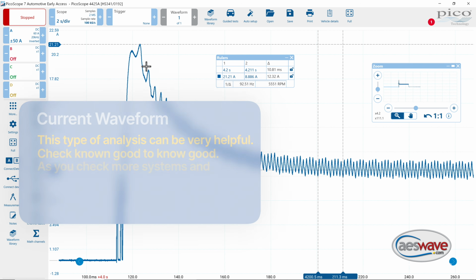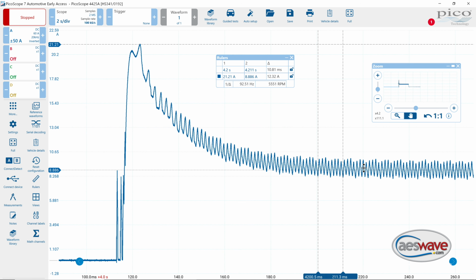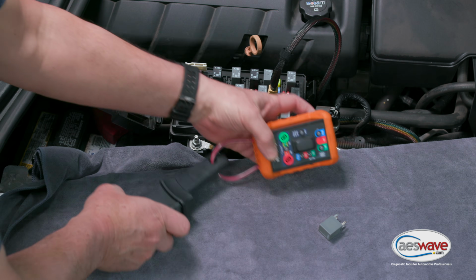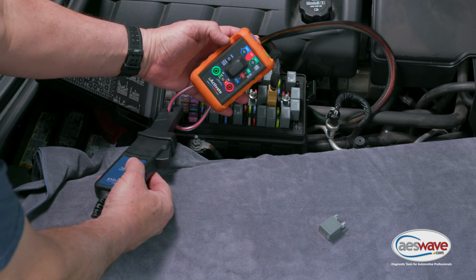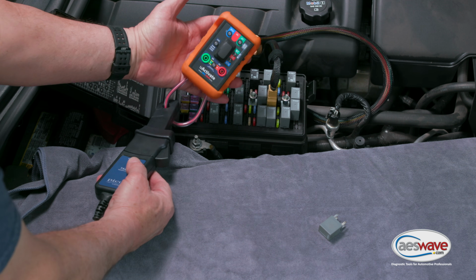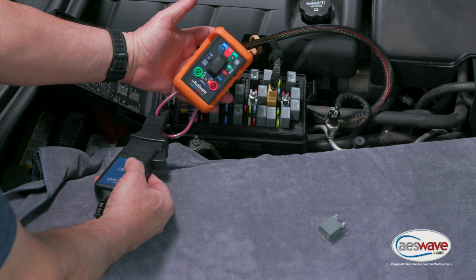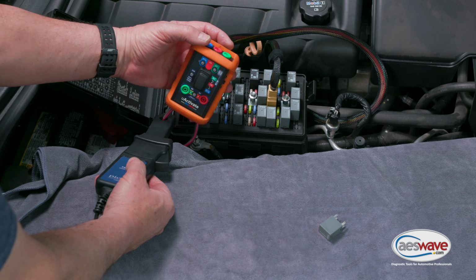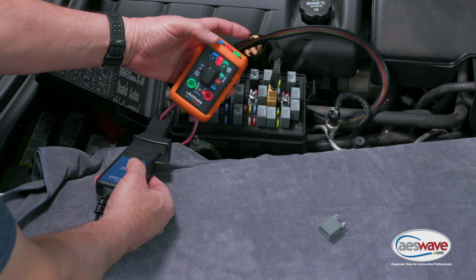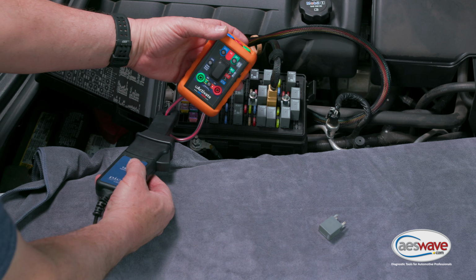We're hitting our peak amperage, 21 amps, that indicates a healthy circuit. And we've got nominal speed, and our operating amperage is about 8 amps. So as you can see, using the uActivate to get into the circuit and interrogate it makes it very, very convenient for you when you're analyzing circuits like this.